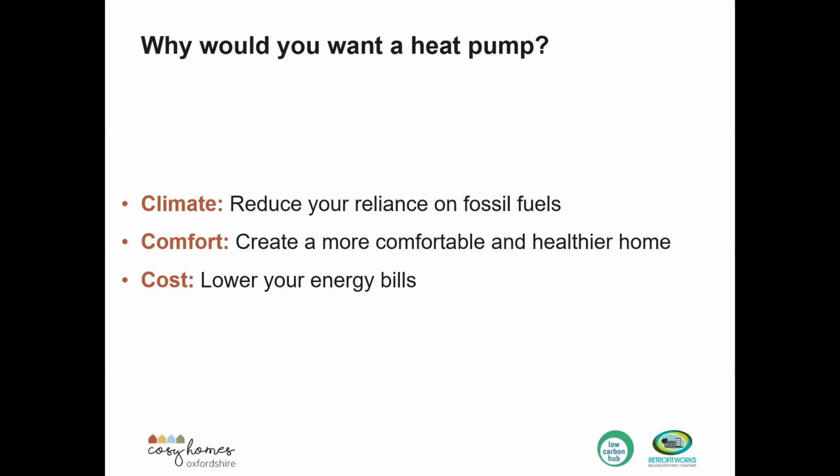If we look at other efficiencies, a gas or oil boiler, depending on its age, can vary. If it's very old, it could be 60% efficient. If it's a modern one, it could be 90% efficient, which means you're losing 10% even with the best gas boiler. At the other end of the spectrum, a lot of people still have open fires. Anybody know the efficiency of an open fire? Less than 40%? Around 10%. It varies, but roughly 90% of the heat is going up the chimney and heating up the birds up there. So that's the context.